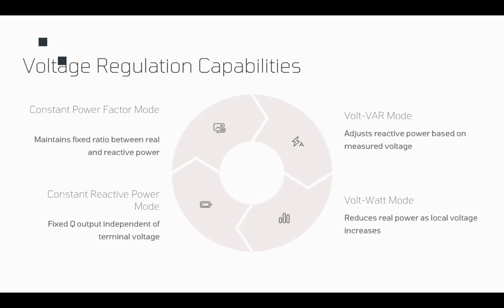Another capability is the volt-var mode, which is a dynamic reactive power control. Okay, and this is the primary dynamic voltage regulation, which is mandated by IEEE 1547. In this mode, the DER adjusts its reactive power output continuously as a function of the measured voltage at the PCC. So it could stabilize the power. When the PCC voltage drops below nominal, we have under voltage, the DER basically injects lagging reactive power, which is a positive reactive power, to support the voltage recovery. And if we have over voltage at the PCC, the DER absorbs leading reactive power, which is a negative reactive power, which mitigates that overvoltage and helps the stability of the system.